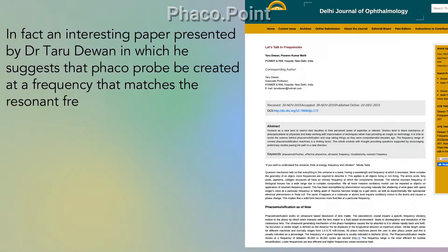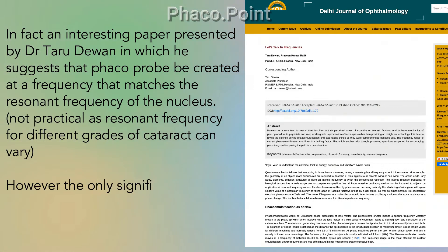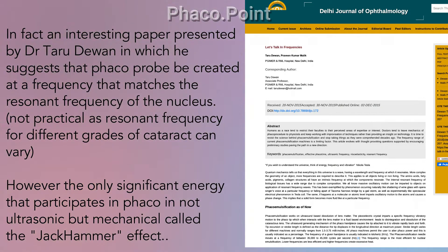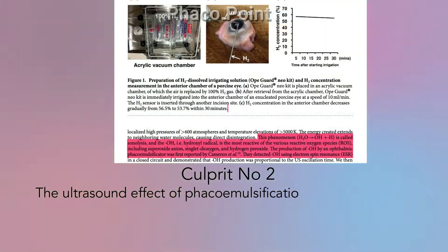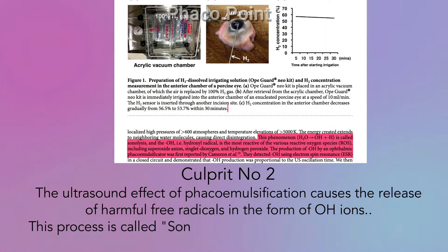This vibratory effect is not used in phaco. An interesting paper by Dr. Taru Dewan suggests creating the phaco probe at a frequency matching the resonant frequency of the nucleus. However, the only significant energy that participates in phaco is not ultrasonic but mechanical — this is called the jackhammer effect. So culprit number two is that ultrasound during phaco causes the release of harmful free radicals in the form of hydroxyl ions.